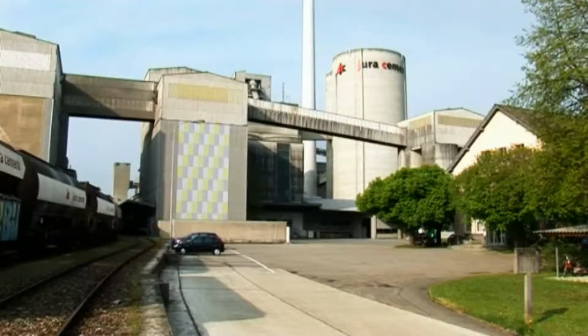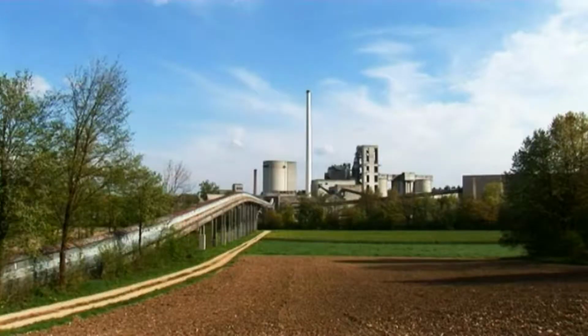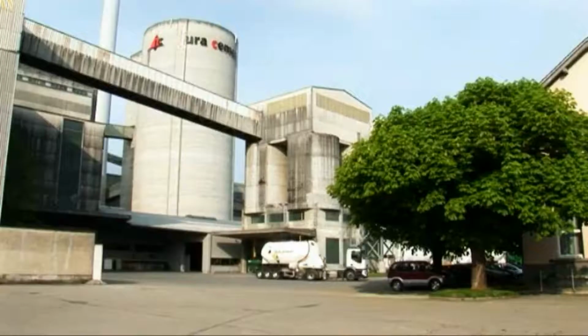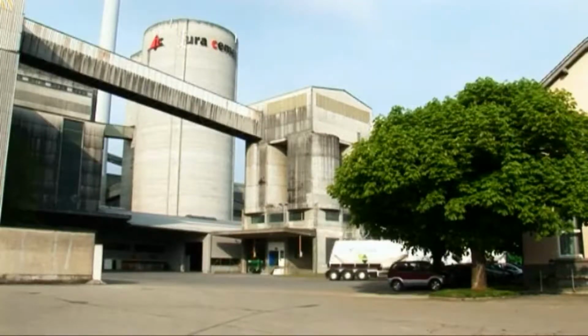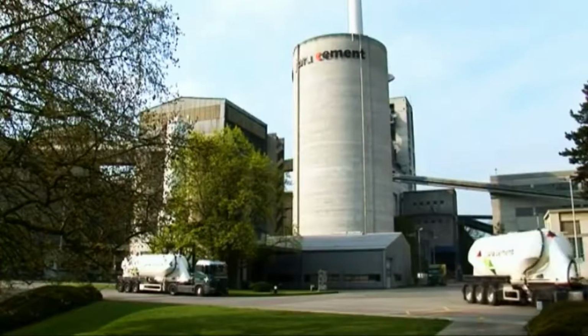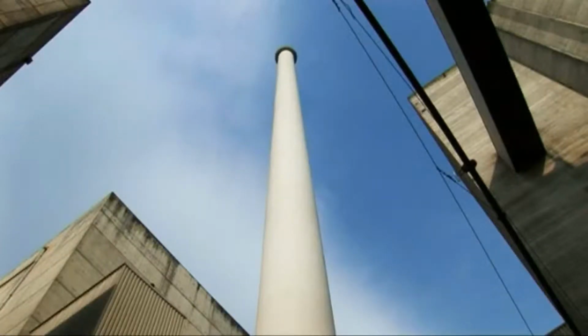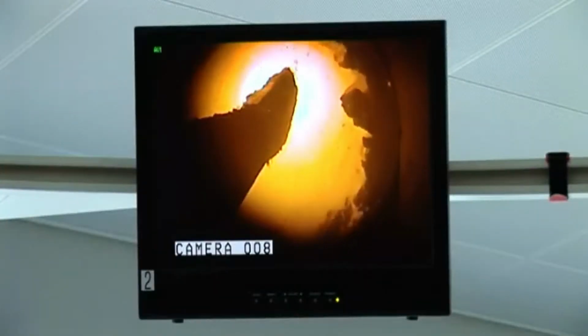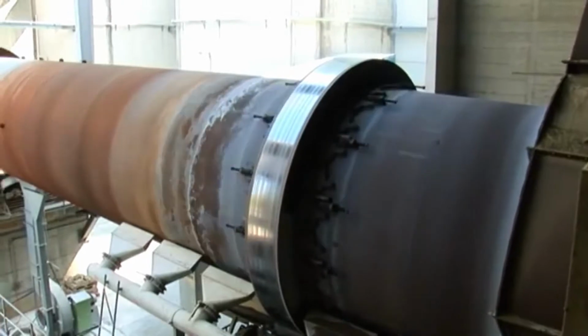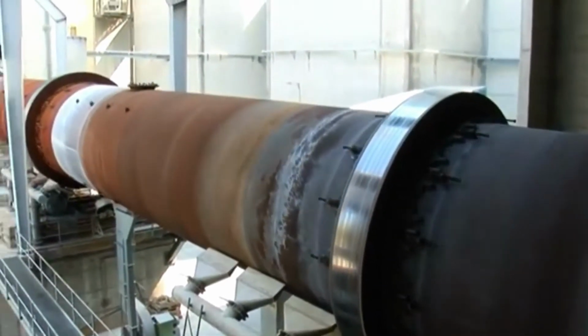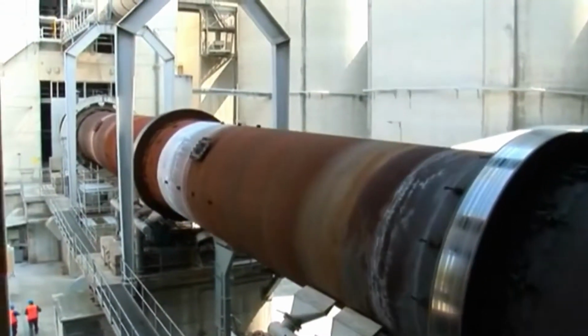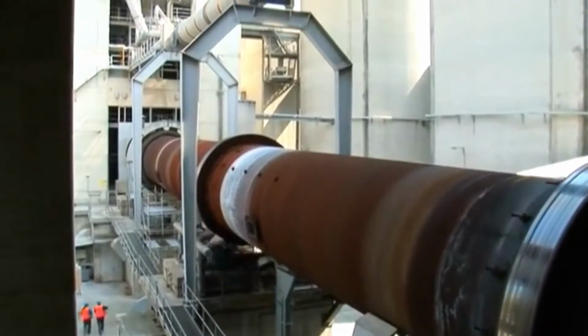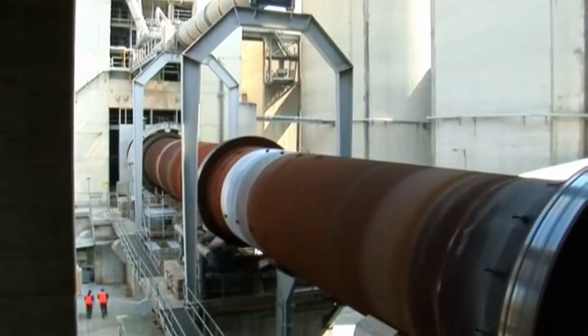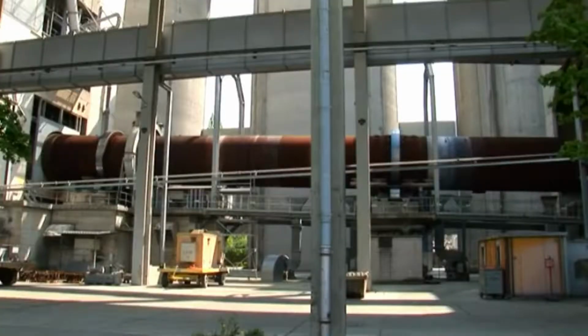January 2009, and the world's first ACS 2000 6 kilovolts medium voltage drive goes online at Jura Cement, Switzerland's second largest cement producer. The 550 kilowatt drive is used on the clinker cooler exhaust fan, located immediately after the 2,000 tons, 56 meter long Polysius kiln. The fan plays a critical role in the cement making process.